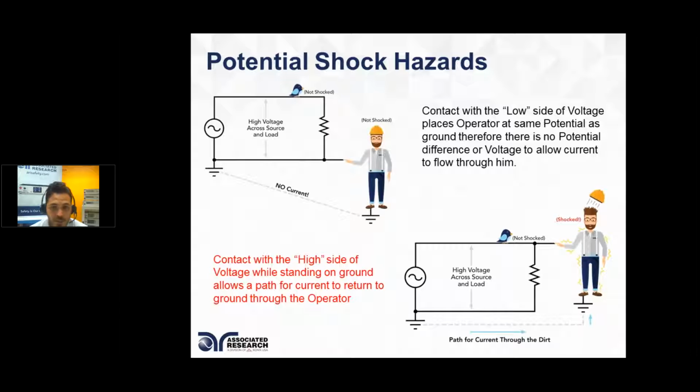Again, the bird, same place, right? He is, or it is, an open circuit, right? There's no path for current to flow through the bird, but now our operator is in contact with the high side of voltage.